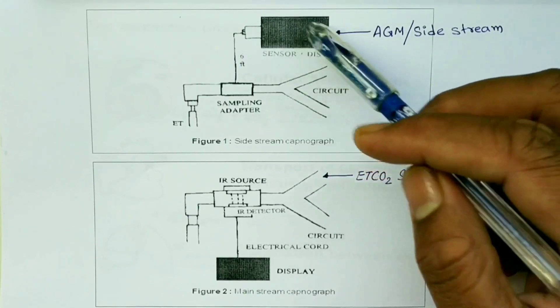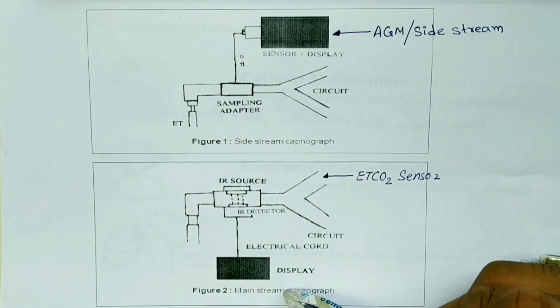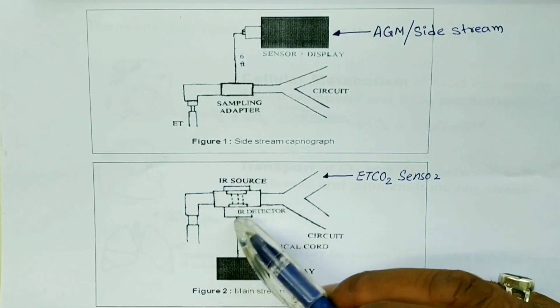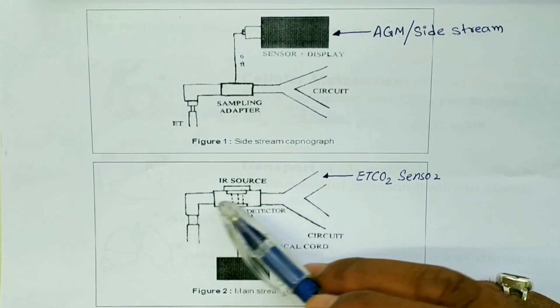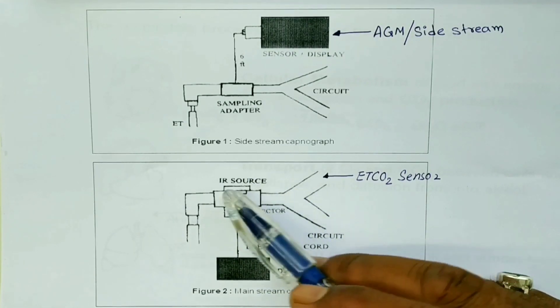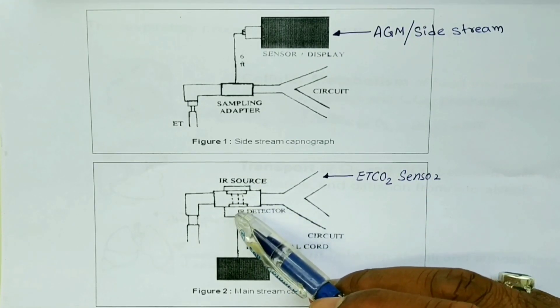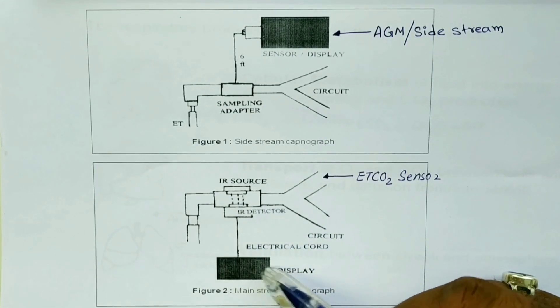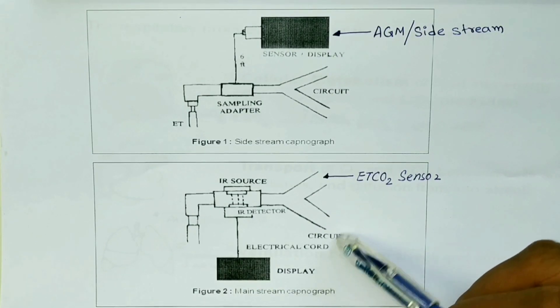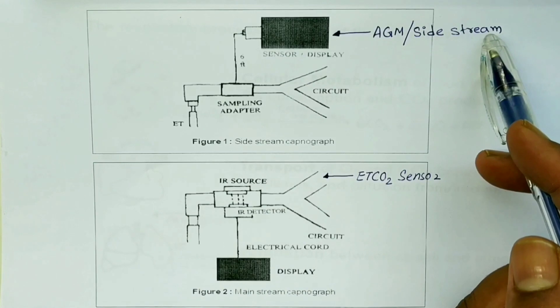In mainstream ET CO2, the ET CO2 sensor is directly over the ET tube. That is, the IR source, the infrared source, and the infrared detector are on the ET tube, and there signal transmission and reception takes place. Then it gives the data to the main recorder and displays the ET CO2 values. This is the ET CO2 sensor and this is AGM or side stream method.